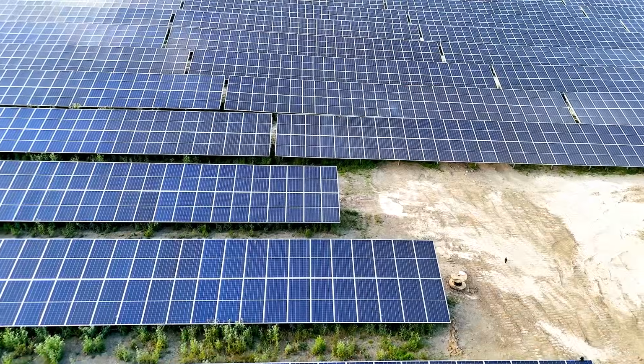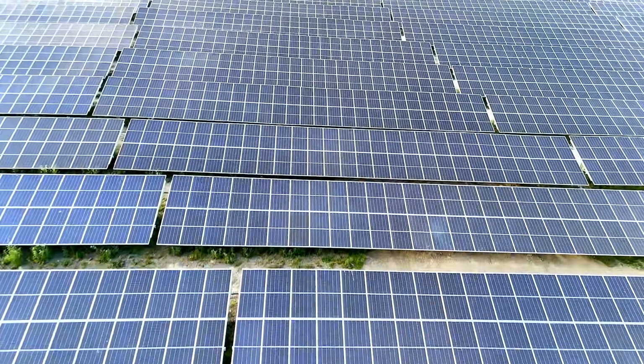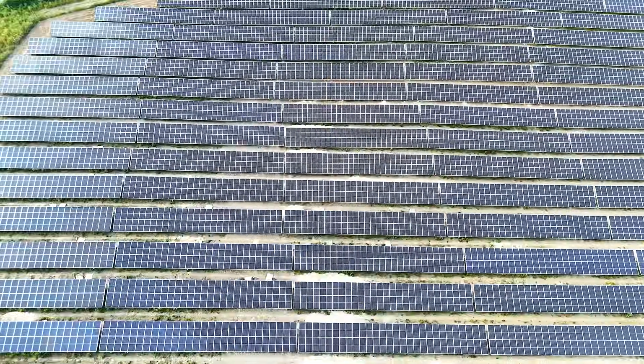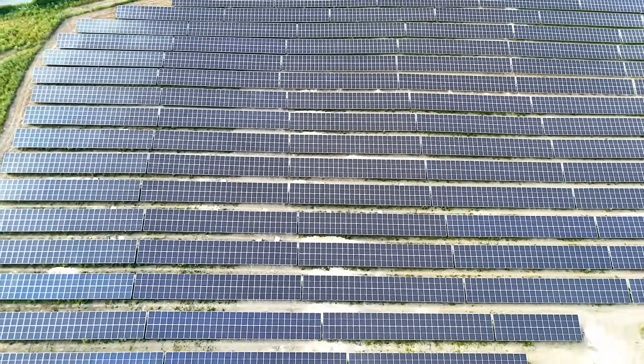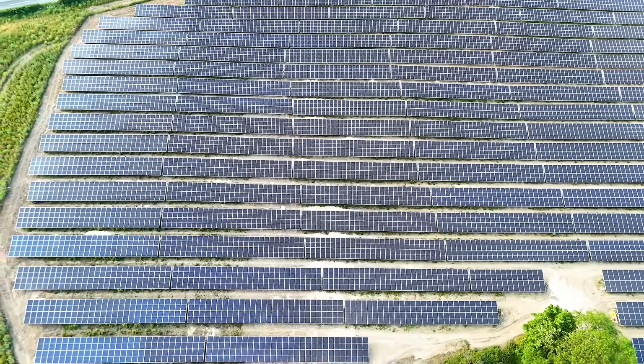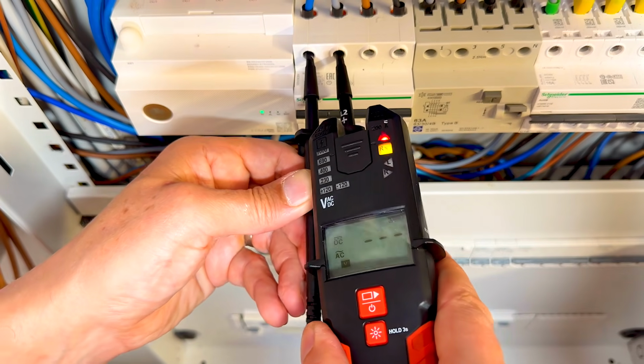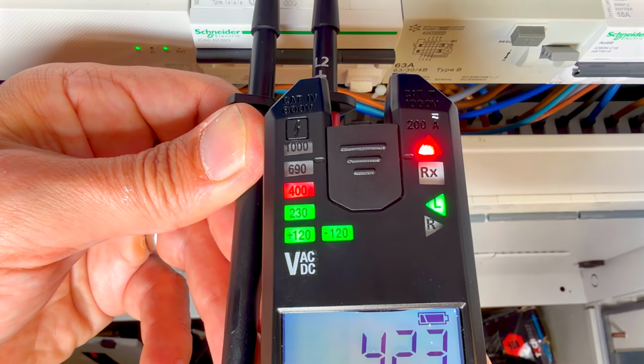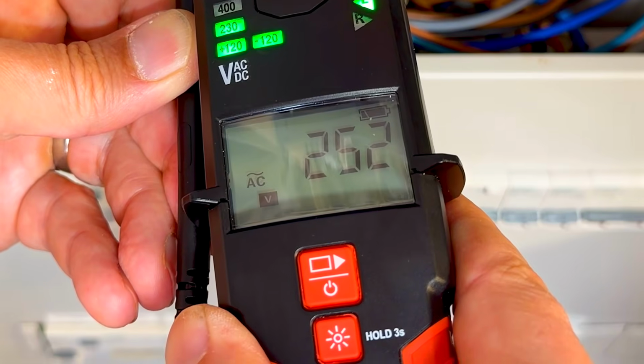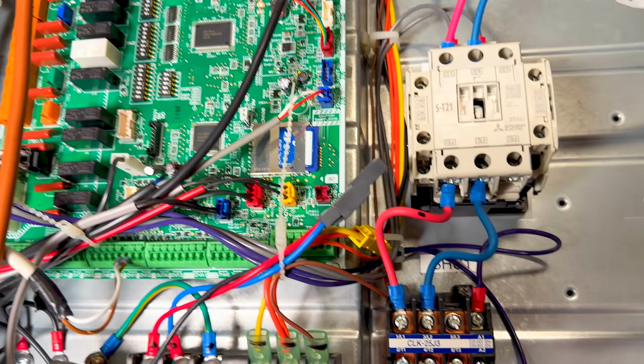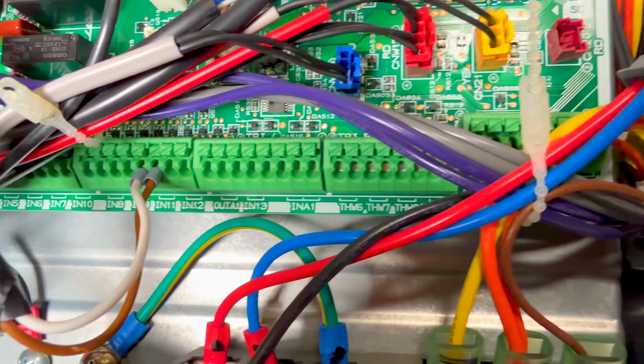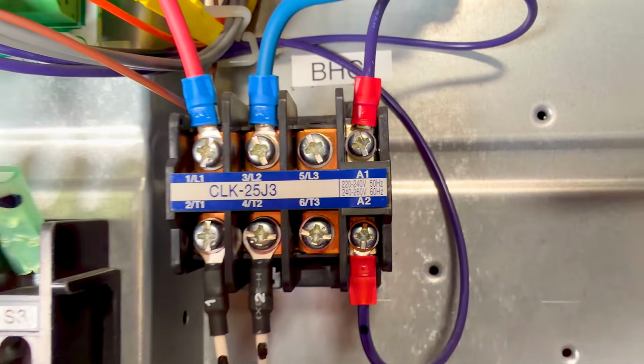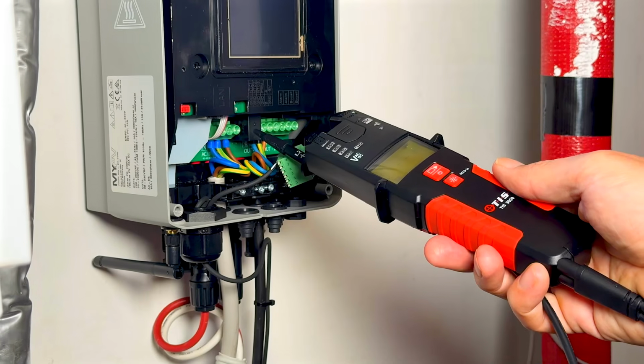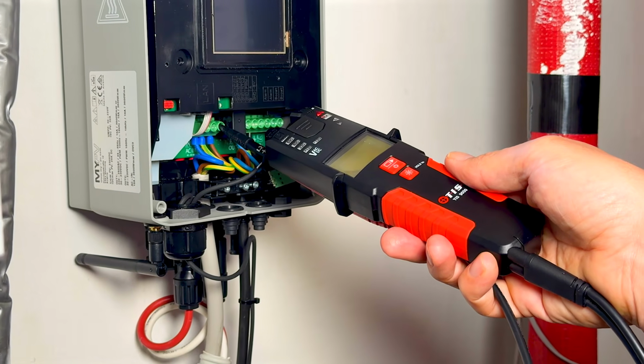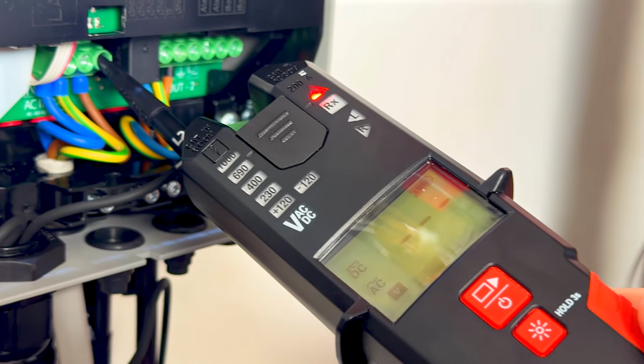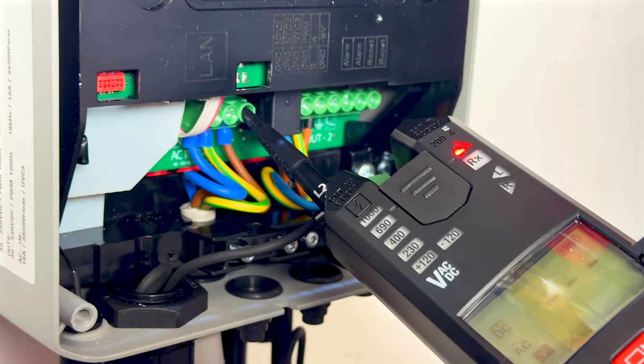If you want to measure voltage levels, the tester can handle up to 1000 volts AC and 1500 volts DC, making it ideal for larger solar strings. You can view that voltage either on the bar graph for a quick indication or as an exact value on the screen when you need precision. There's also a low voltage range giving you better resolution below 10 volts, which is particularly useful when you're working with control signals. It can also detect the presence of voltage using just a single probe, which is handy if you need a quick check to see if a circuit is live.